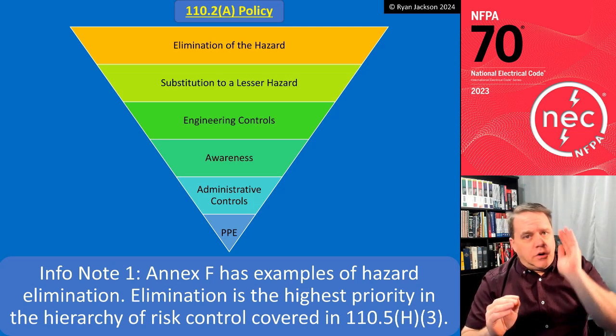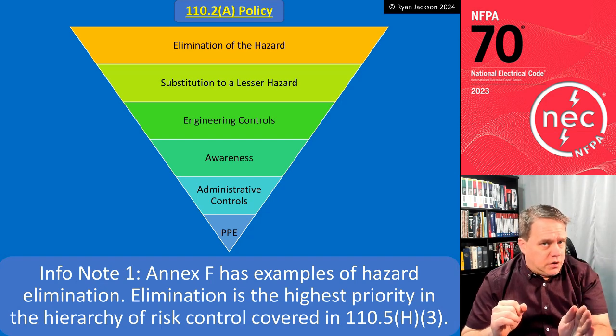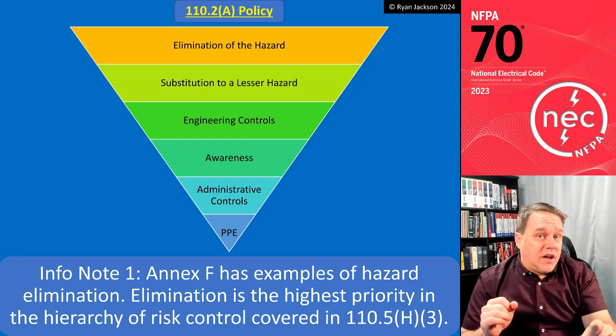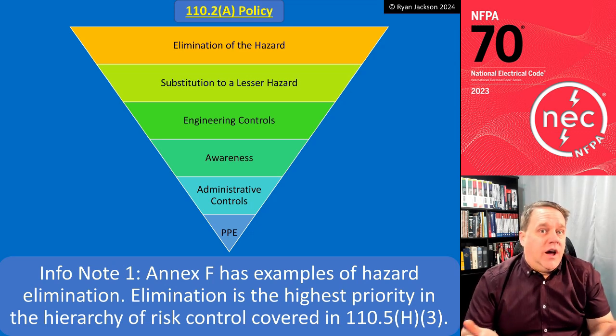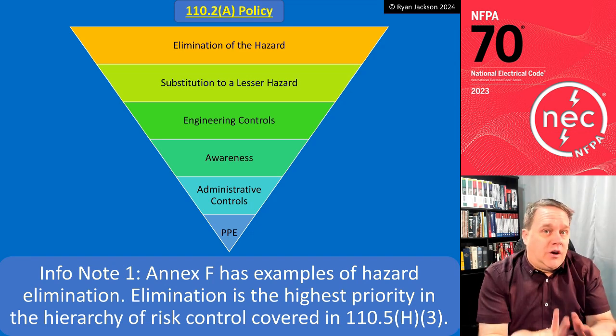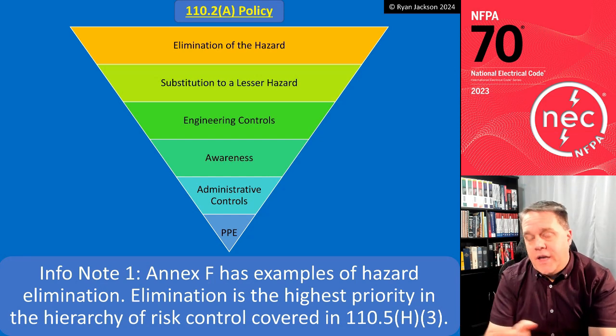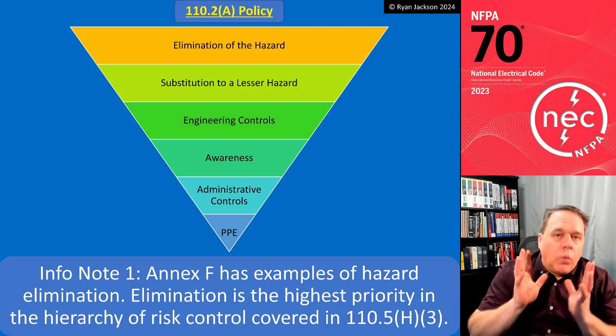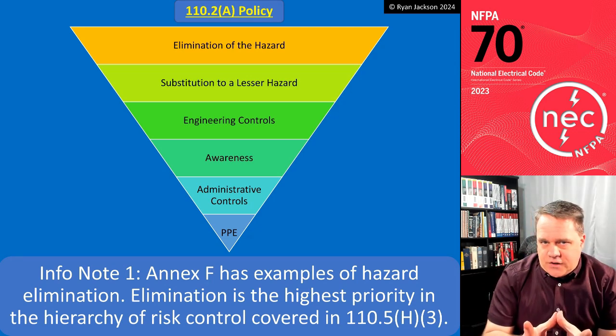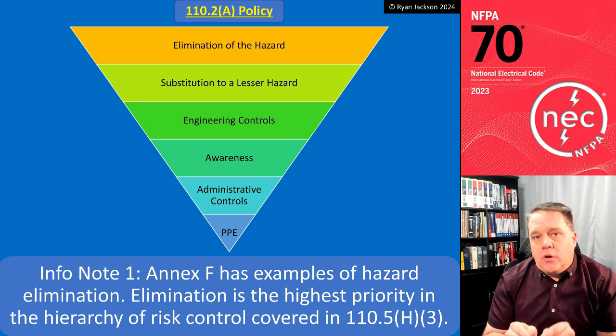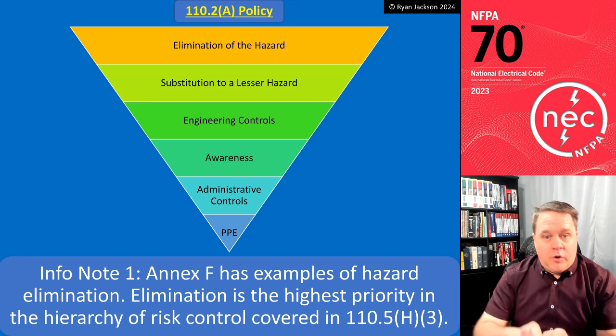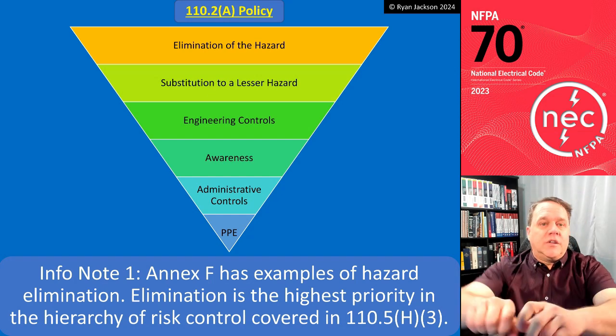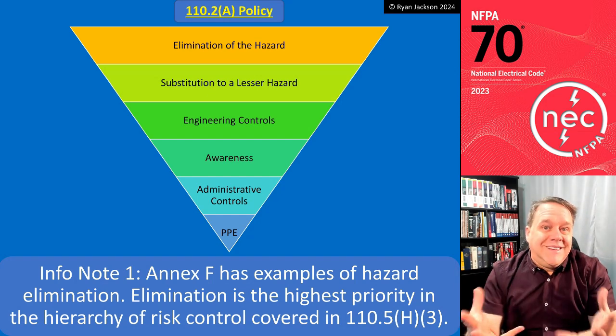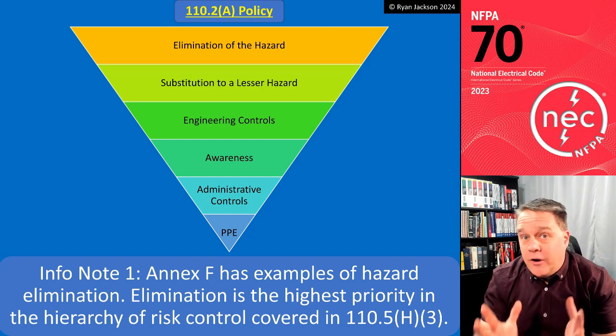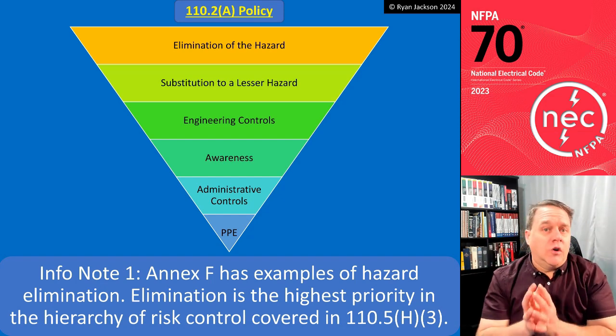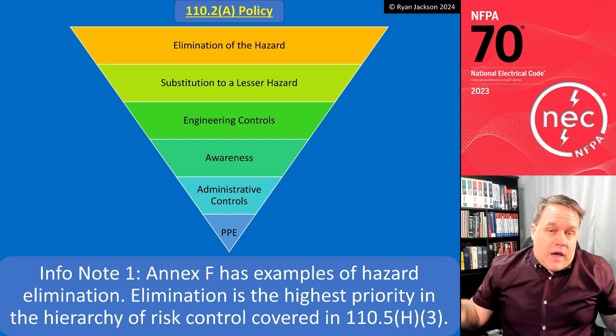Now be careful here. There's two different types of energized work. There's troubleshooting, diagnostics, right? That has to be done energized a lot of times. I can't measure for voltage if it's not on, right? I can't troubleshoot why something is behaving in a certain way if it's not on. We're okay with diagnostics and troubleshooting. What we are not okay with is repair work, where you're actually going in there and tightening screws and using wrenches and everything else inside of energized equipment. We don't want people repairing equipment. That can almost always be done while it's off. Troubleshooting? Hey, if you can turn it off, turn it off.